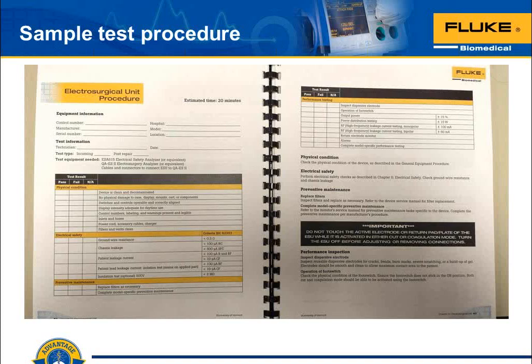give you a little anecdote about cleaning. In the first hospital in which I worked, even before I had quite finished my associate degree in medical electronics, we were testing older Valley Labs SSE2, Ks, and Ls back in the day. And our hospital, for some reason, just was a lint generator. I mean, there was lint all over the place, and the housekeeping staff really did a good job of keeping it so it wasn't visible. But I'll tell you that anything that has a fan unit in it for cooling also pulls air from the room inside those kinds of devices, and sure enough, those devices are going to fill up with that lint.